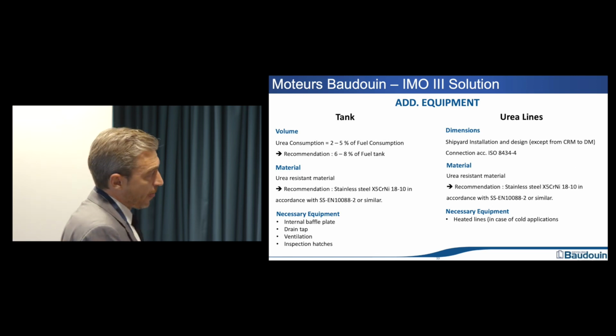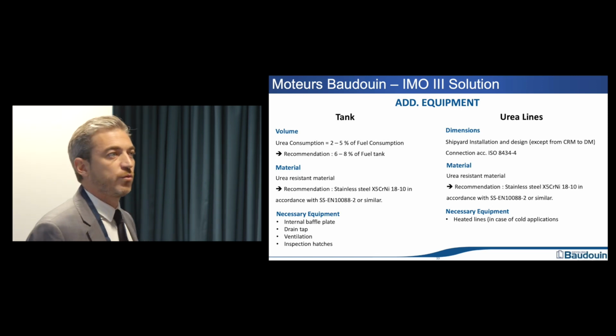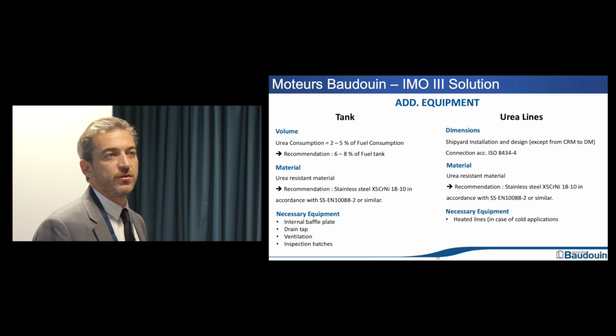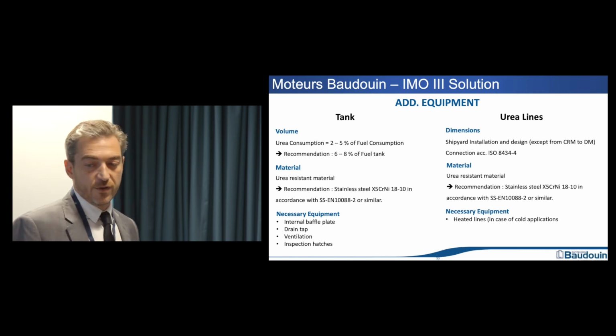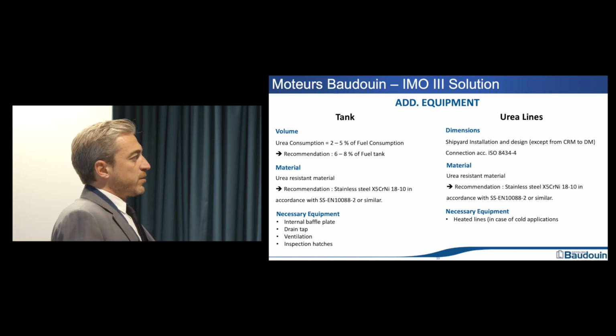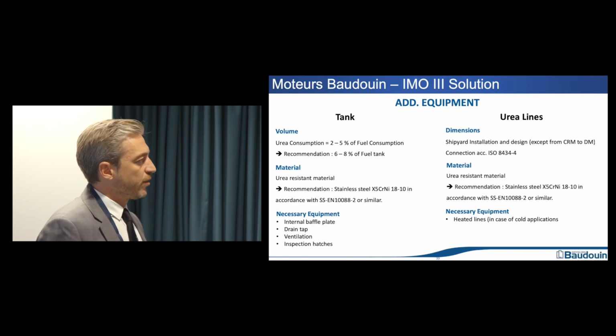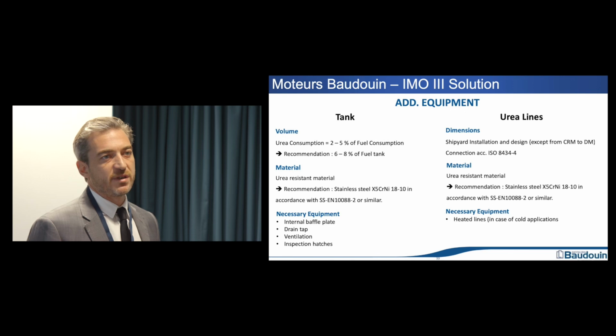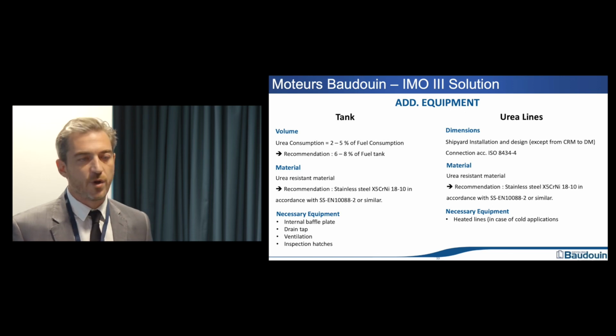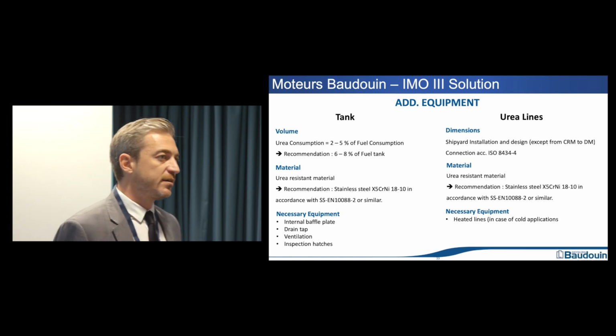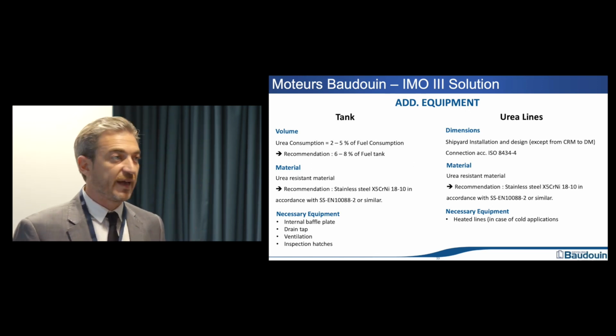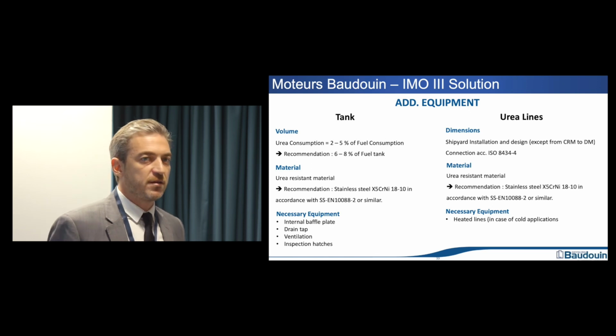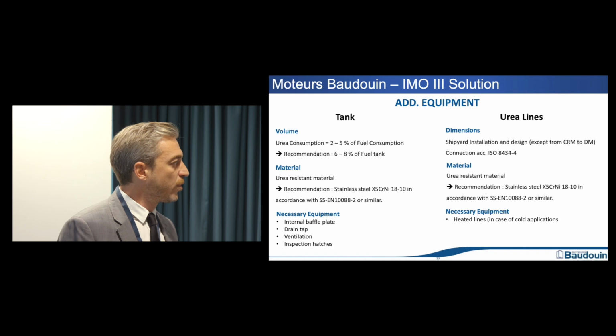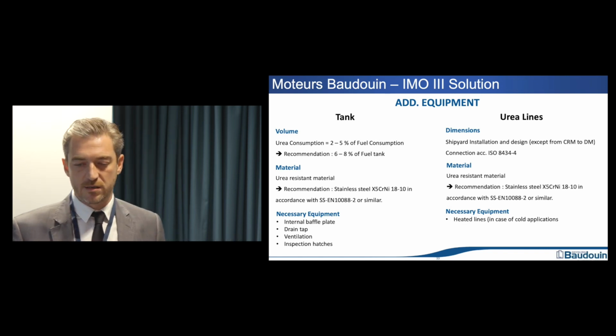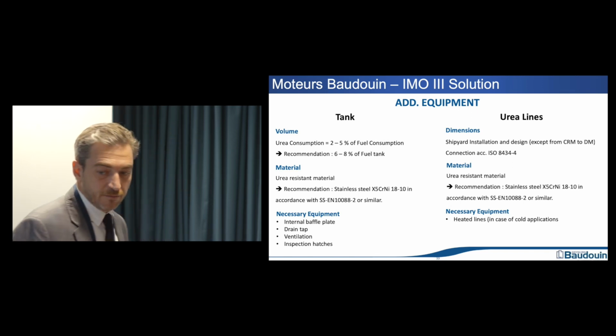About the tank: we don't supply it, but we help recommend the dimensioning and shape. Urea consumption, depending on load and application, represents approximately 2 to 5% of fuel consumption. We always recommend a tank representing 6 to 8% of the fuel tank size, but this depends on whether you want a bigger or smaller refueling frequency for urea, which is at your discretion.